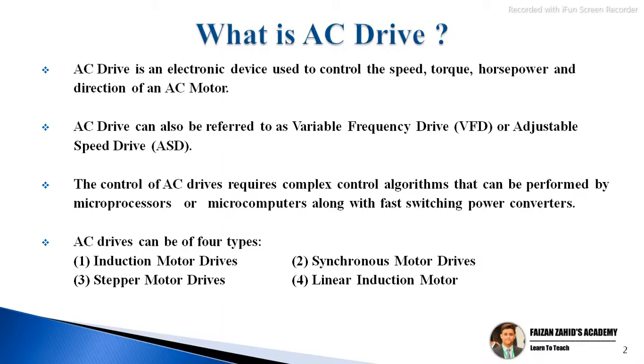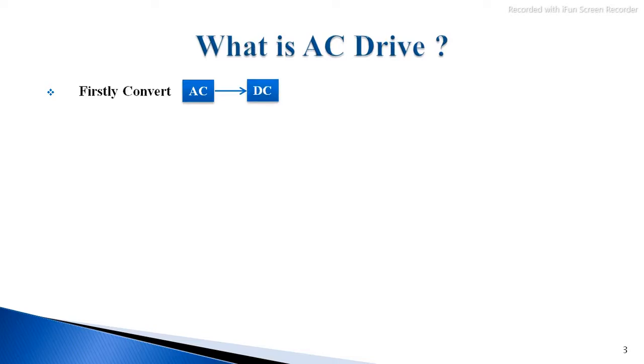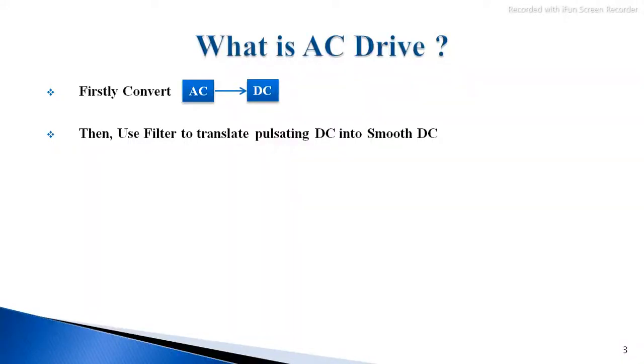Now let us discuss how AC drives work. Firstly, AC is converted into DC using a rectifier. Then a filter is used to translate pulsating DC into smooth DC, because after rectification the output we get is pulsating DC. So to convert that pulsating DC into smooth DC, we use a filter.